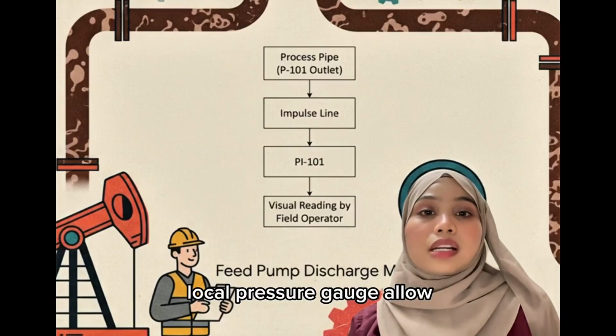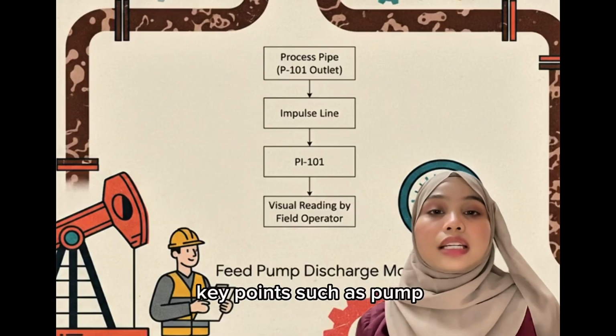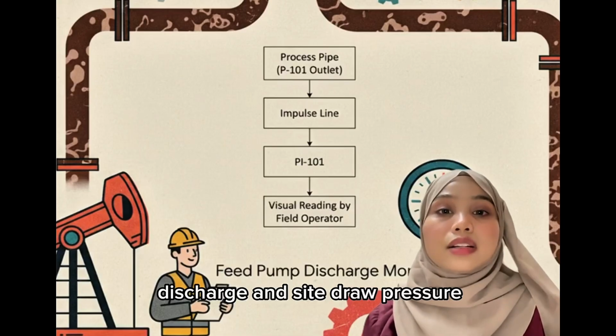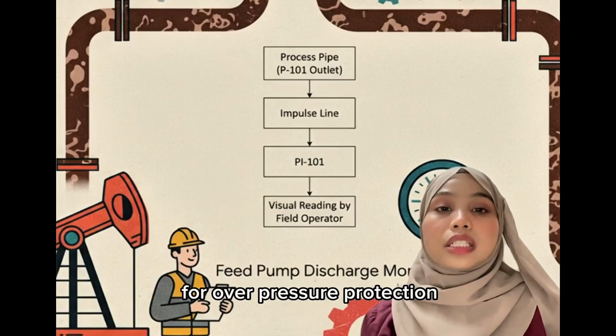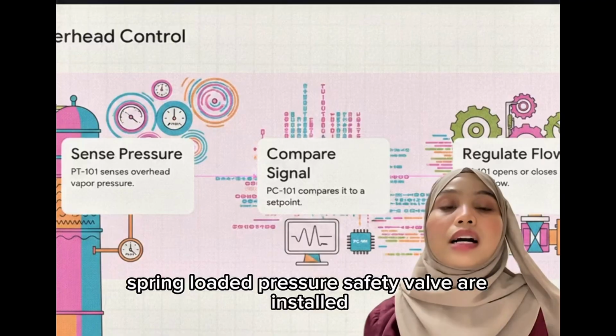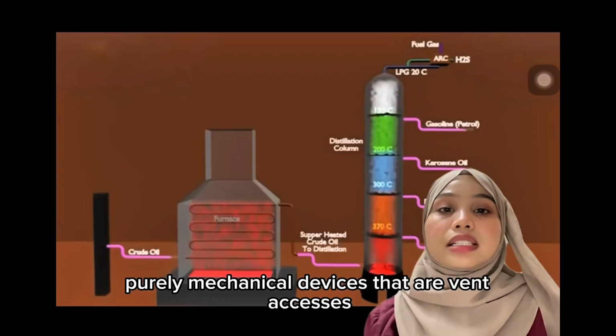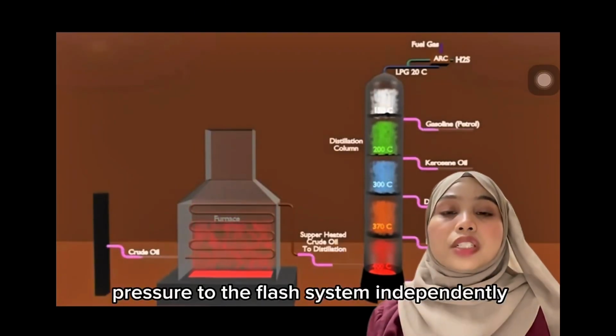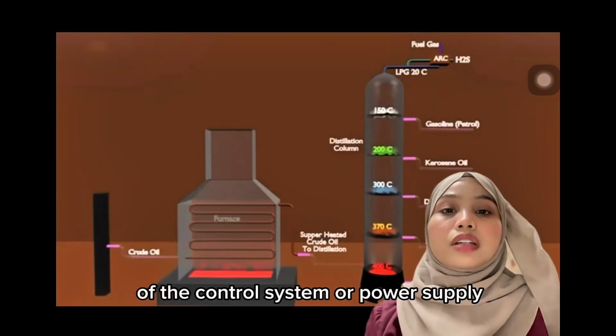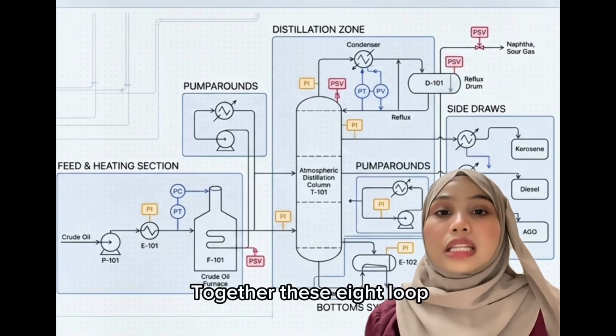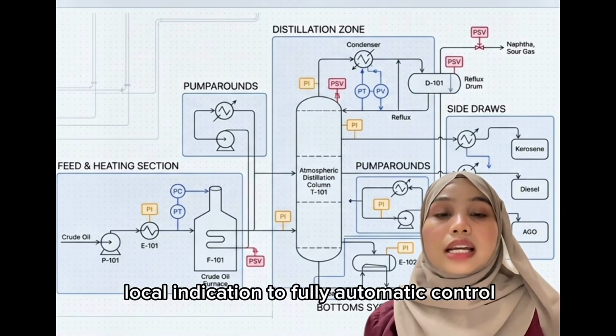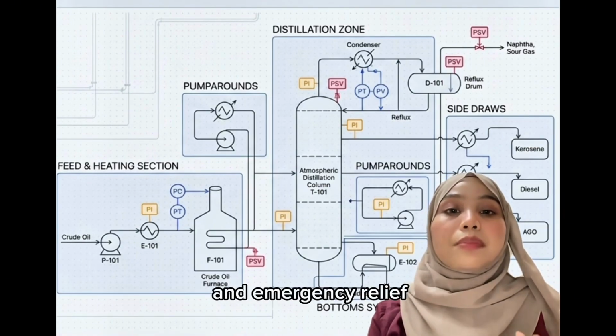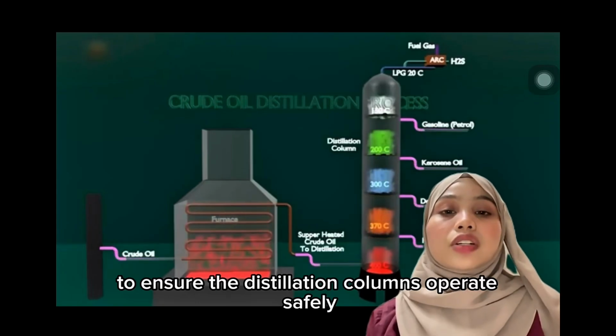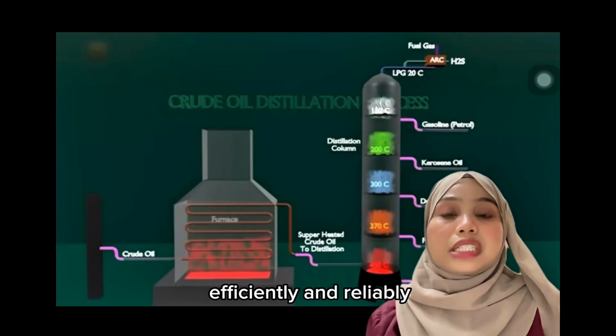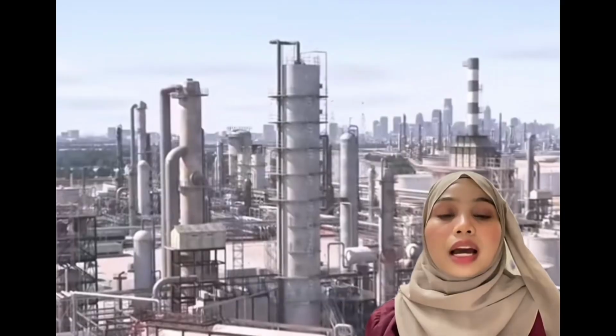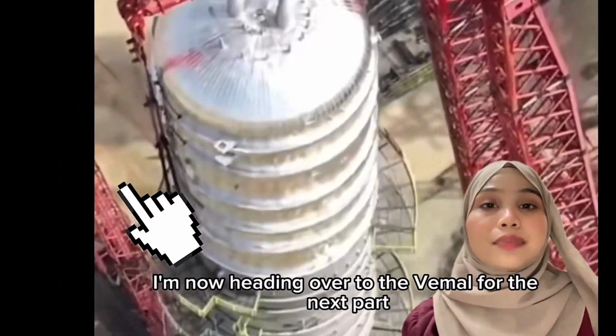Local pressure gauges allow field operators to manually check key points such as pump discharge and side draw pressure. For overpressure protection, spring-loaded pressure safety valves are installed. These are purely mechanical devices that vent excess pressure to the flare system independently of the control system or power supply. Together, these 8 loops, ranging from simple local indication to fully automatic control and emergency relief, ensure the distillation columns operate safely, efficiently, and reliably. That's all from me. I'm now handing over to VEMAL for the next part.